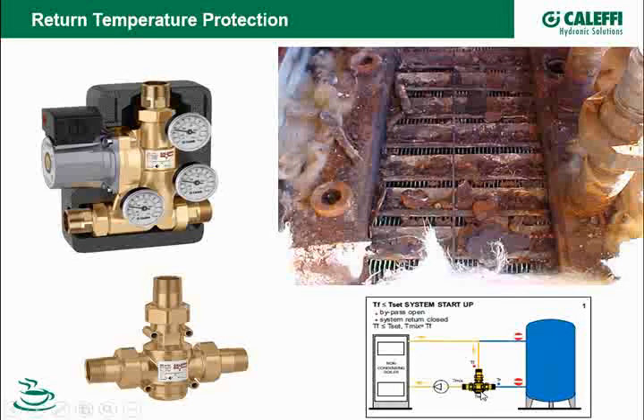This is just a fixed temperature valve that you put right in the piping like this. Basically, it allows the water to bypass back to the boiler until the temperature is to the point that it's going to prevent this boiler from condensing. Usually this will be set around 130 degrees to make sure that this boiler always sees 130 degrees here. Once that temperature is satisfied, it'll allow this port to open and go out to your buffer tank, your system, or something like that. We at Caleffi offer a couple versions of that, just a basic valve like this that you can pipe in with your own pump, and we have them with a pump built into it.